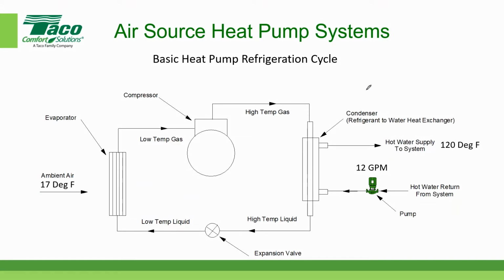So as the name implies, an air source heat pump is actually an air to water heat pump. And in this configuration, we're showing the heat pump producing hot water. So it's producing 120 degree Fahrenheit hot water that it's sending out to the system, hot water supply. And the return water for this type of unit is roughly around 110 degrees Fahrenheit. You can have a higher delta T, but for the most part, they run within that range.